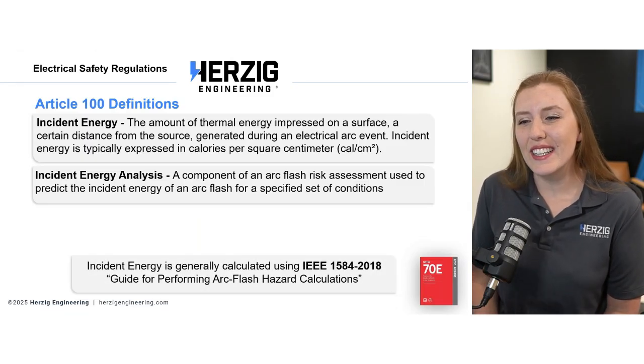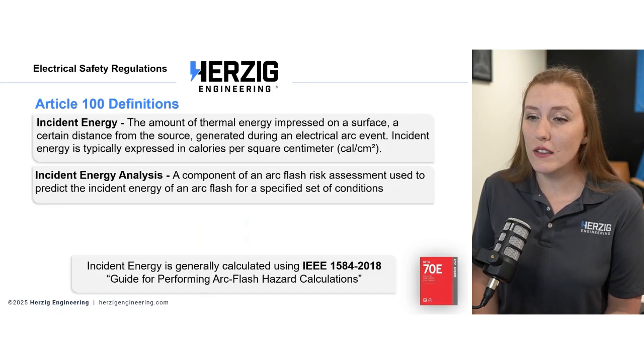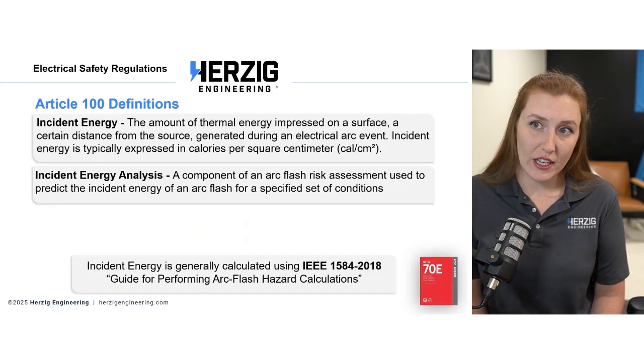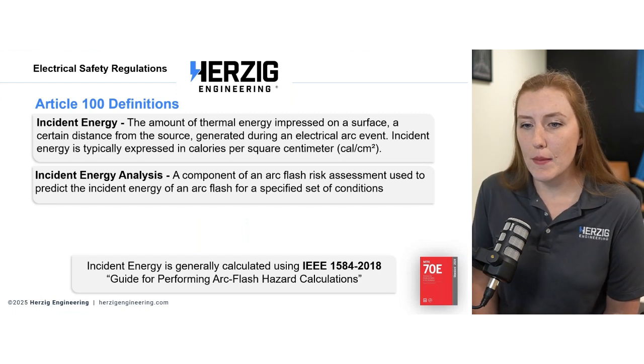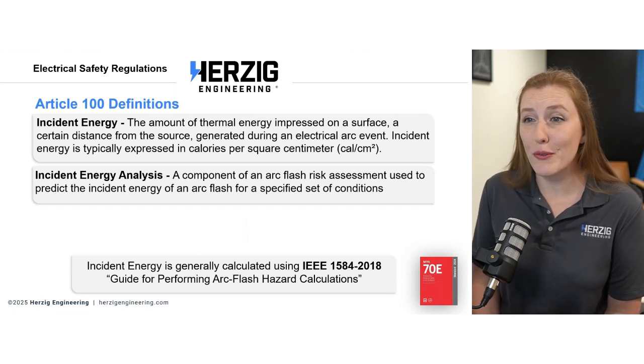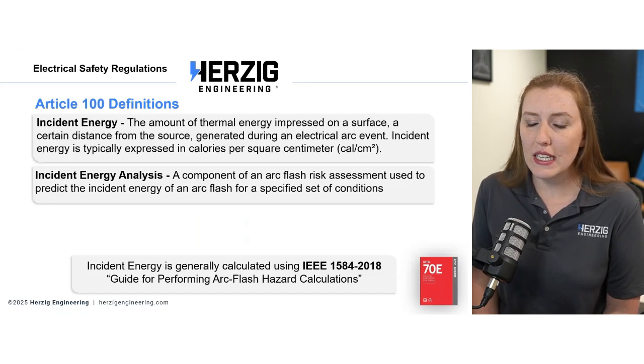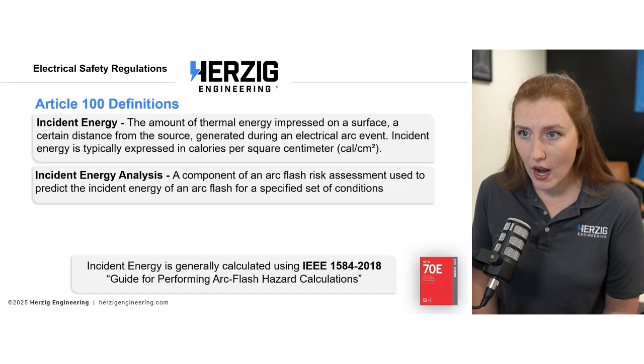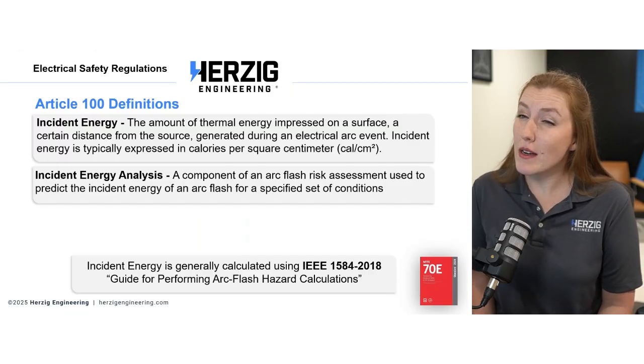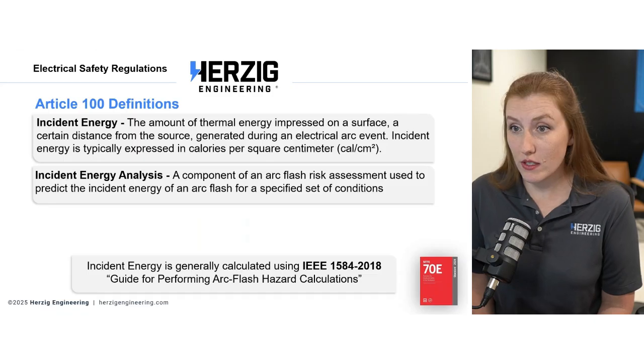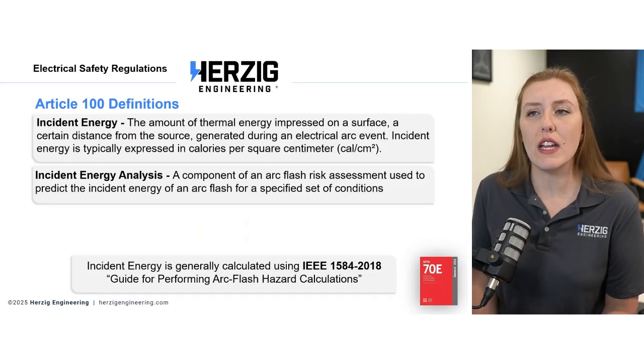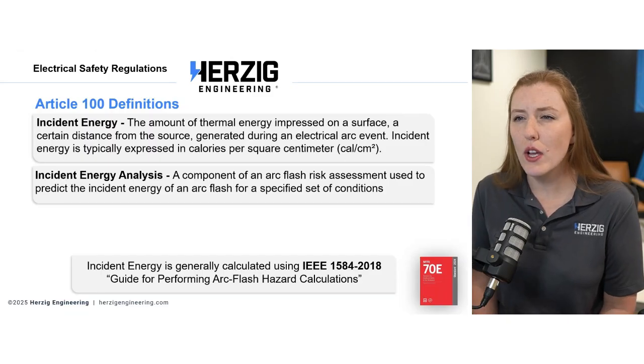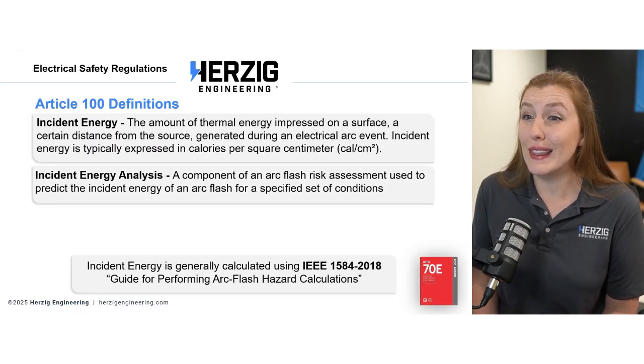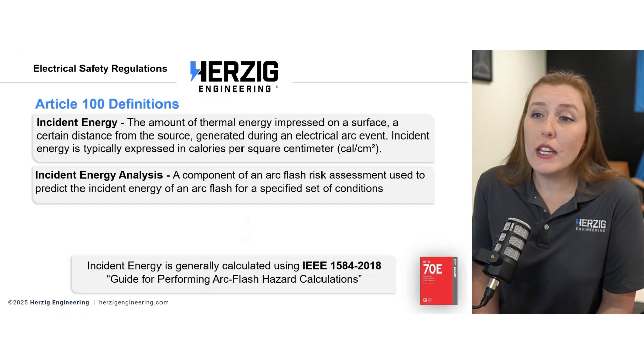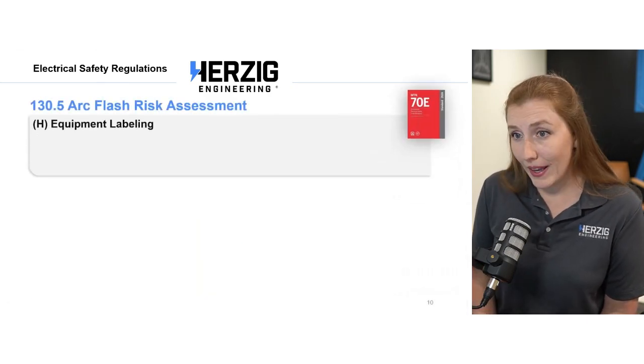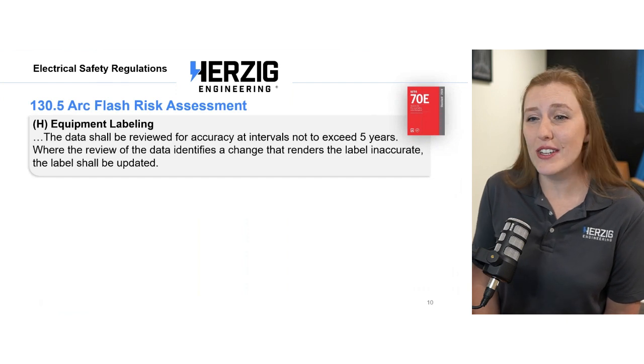Incident energy is generally calculated using the IEEE 1584 Guide for Performing Arc Flash Hazard Calculations, and there's the 2018 edition that came out. So certainly if it's been since before 2018, you for sure need to get it updated because there's actually better, more robust, more accurate calculations out there now based on more data, more test results from actually having arc flash events calculated versus tested in a lab to see how close those calculations are. So this is a lot closer. It's supposed to be updated every 5 years anyway, but there's just a little extra incentive in case you haven't been keeping up with that.